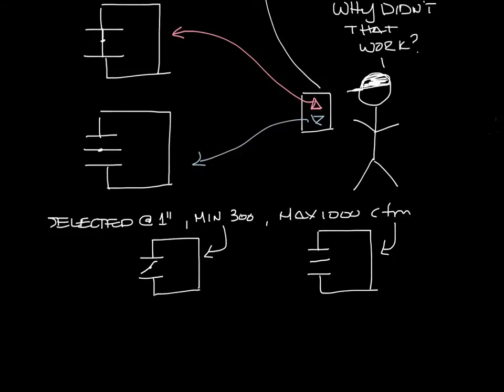So let's say the space is 75 degrees. If the inlet pressure is 1 inch, when he turns the thermostat all the way down, say to 65 degrees, and the space is 75 degrees, the controller thinks it needs more air to cool down the space and it will drive the damper to maximum CFM, which at this 1 inch pressure would be almost full open.